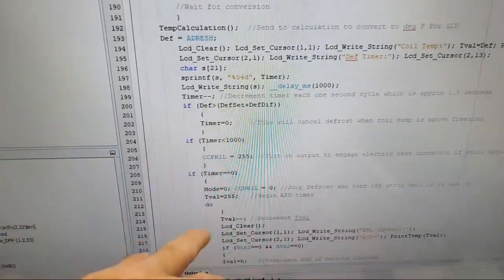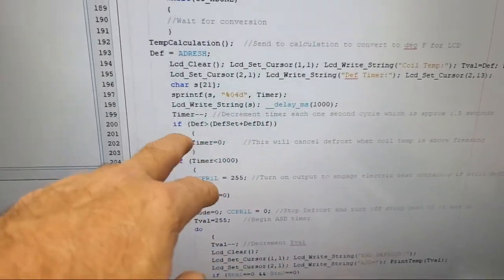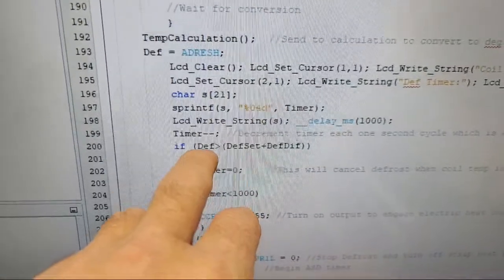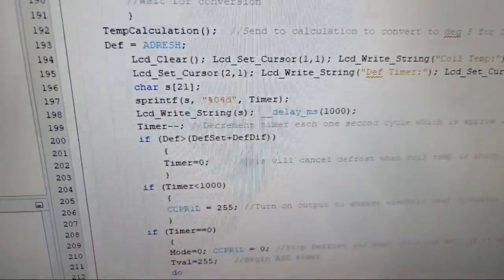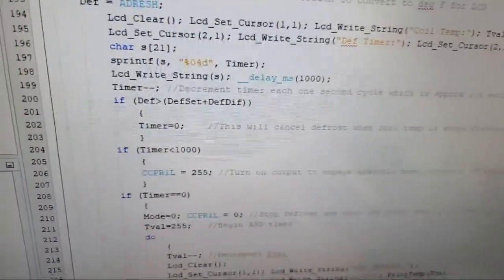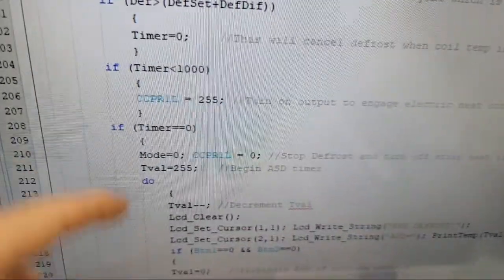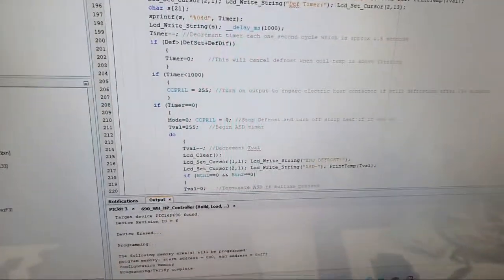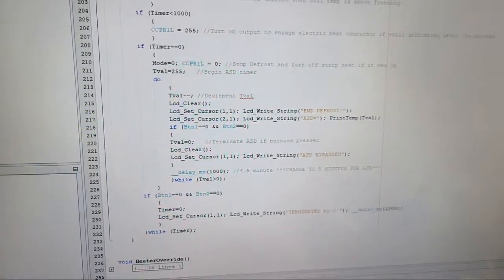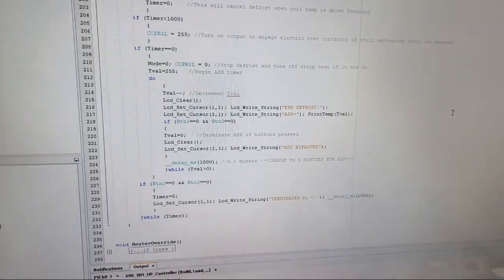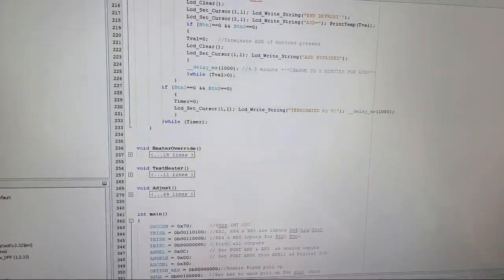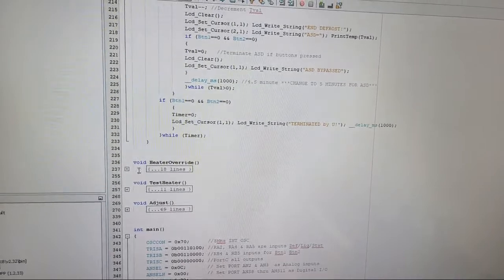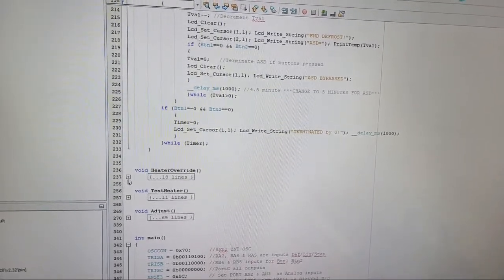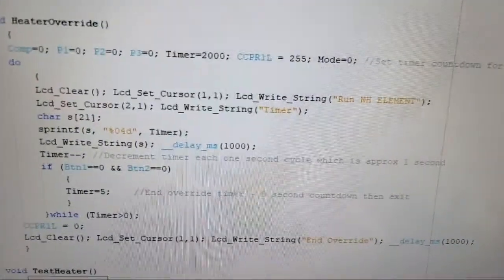And in the code, I think if the defrost sensor is above the set point plus the differential, it just turns the timer to 0, and that's the only variable I need to change, and then automatically, because of the other code, it's just going to leave. So pretty simple stuff in there. And then I can push the buttons. It says terminated by you. I'm sure I put an expletive or something in there. And I have other things. I have a way to override a heater just to test it. And then I think I have a function just to override it and just run electric. So it says run electric.